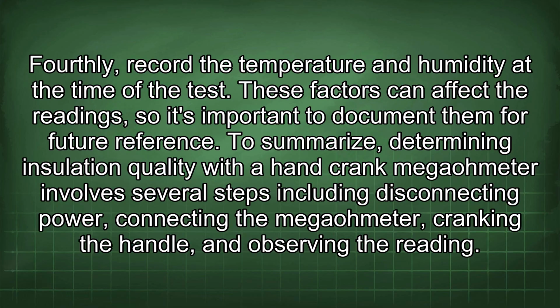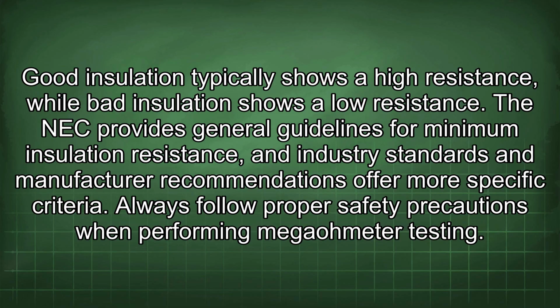To summarize, determining insulation quality with a hand crank Megaohmeter involves several steps, including disconnecting power, connecting the Megaohmeter, cranking the handle, and observing the reading. Good insulation typically shows a high resistance, while bad insulation shows a low resistance. The NEC provides general guidelines for minimum insulation resistance, and industry standards and manufacturer recommendations offer more specific criteria. Always follow proper safety precautions when performing Megaohmeter testing.